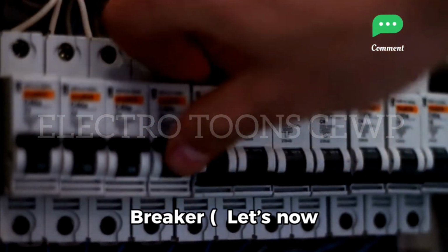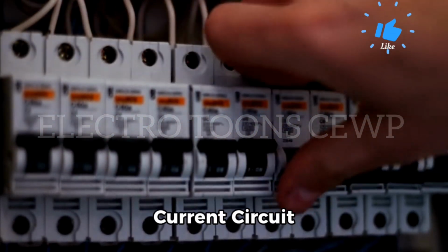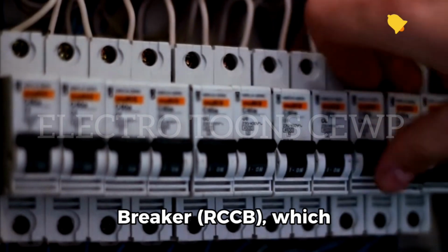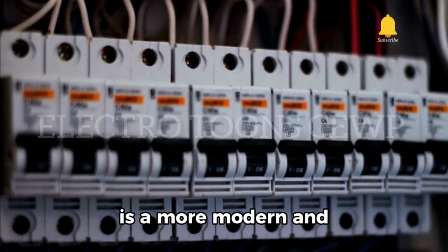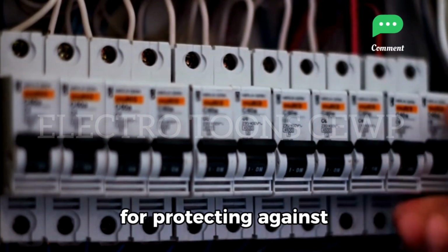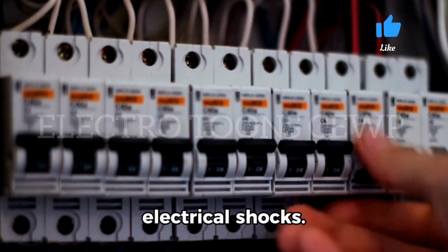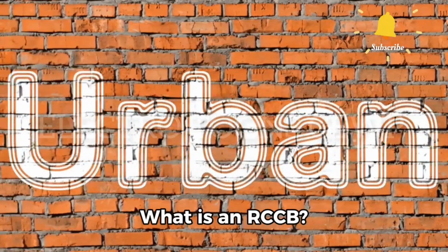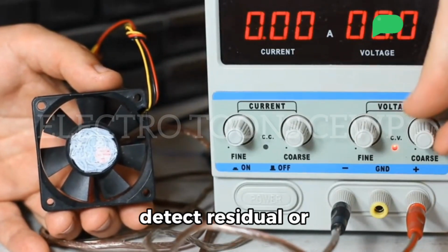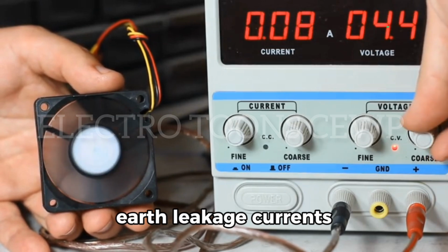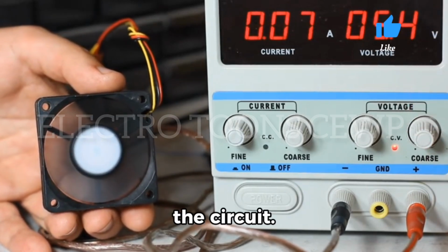RCCB, residual current circuit breaker. Let's now discuss the residual current circuit breaker, RCCB, which is a more modern and commonly used device for protecting against electrical shocks. What is an RCCB? An RCCB is designed to detect residual or earth leakage currents caused by faults in the circuit.